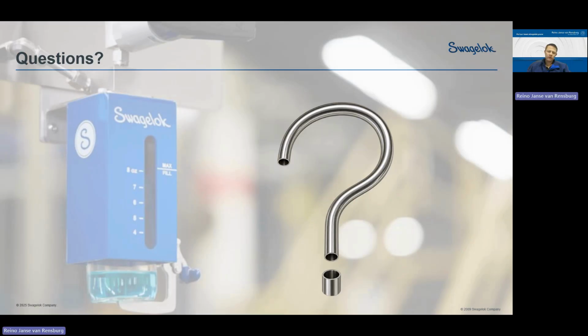Yes, because also you don't want to take a grab sample after it goes through your fast loop filter, because then you're filtering unnecessary things. Exactly. Because your bottle, or your cylinder, is not susceptible to impurities. If there's a little bit of impurities in there, it's not going to make any difference to your bottle, whereas you obviously can't have that in your online analyzer. So it's better to take it on the fast loop or as close to that nozzle, depending on where your preconditioning system sits.